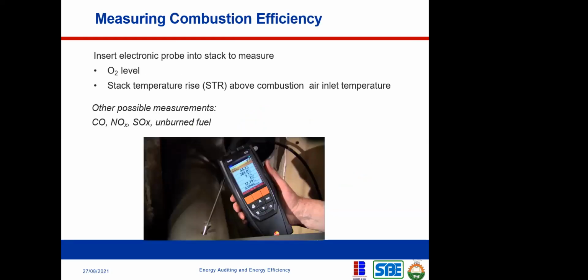So how do we measure combustion efficiency? There's a tool that enables us to measure that. For you to be able to measure your combustion efficiency, you need to insert an electronic probe into the stack. Now, what is the stack? The stack is the exhaust pipe. If you're combusting a fuel in a chamber, there is an exhaust pipe. Your generator is an internal combustion engine, so it has an exhaust pipe. If you want to measure the efficiency of that combustion, you insert this probe into your exhaust pipe.